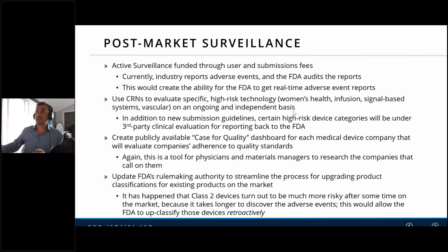And so the combination of understanding that risk profiles will change based not only on the specific product category, but on the specific patient population, combined with the FDA's request to make classification simpler, is going to lead to more traditional 510(k) products moving into that Class 3 category. I mean, it's just going to happen. It's probably happening now. Obviously we don't have visibility inside every company, but you're more than likely going to be having these kinds of conversations in a much more profound way moving forward.